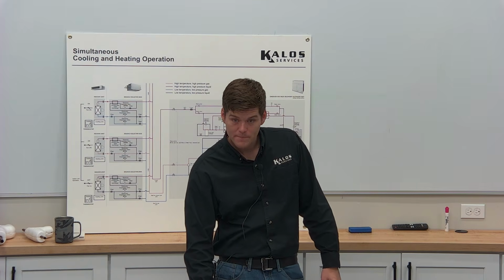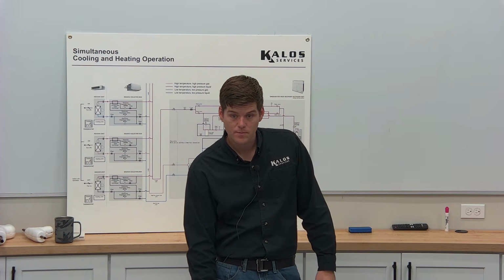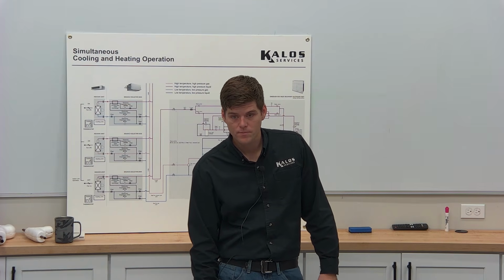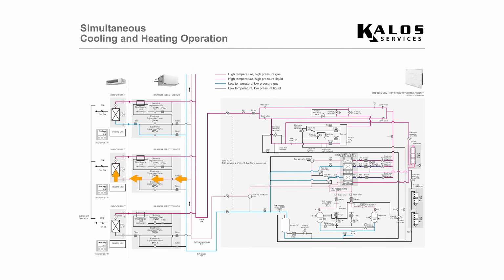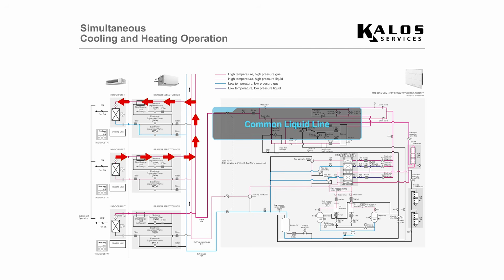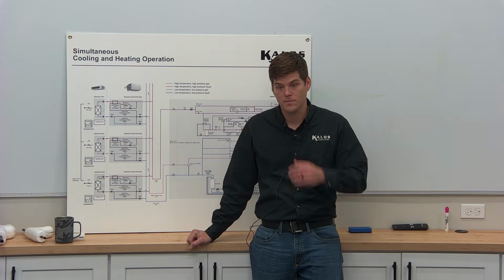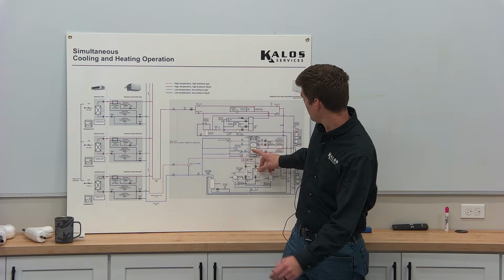So if one air handler is calling in heat mode, gas is getting subcooled, condensed to a liquid, where's that liquid going? It's going to come back over here on the common liquid line, and it's going to come up over here back to this indoor unit. What if that unit is not calling? Then it'll go back to the outdoor unit.